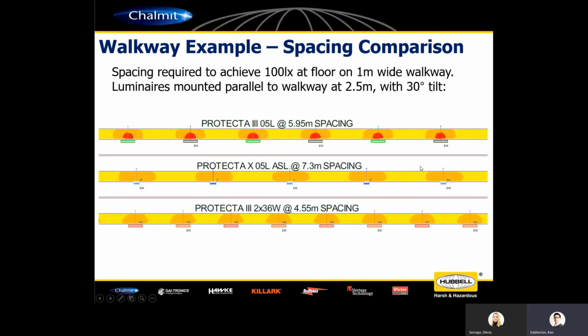Looking at a calculation here, I've looked at the typical spacing required to achieve 100 lux along the floor of a 1 meter wide walkway. All these luminaires are mounted parallel to the walkway at 2.5 meters with a 30-degree tilt, assuming a goalpost type configuration. Looking at the Protectas: the Protecta LED at the top achieves around 6 meter spacing, whereas the Protecta fluorescent at the bottom achieves around 4.6 meter spacing. Protecta X is dramatically greater than that, at 7.3 meter spacing.